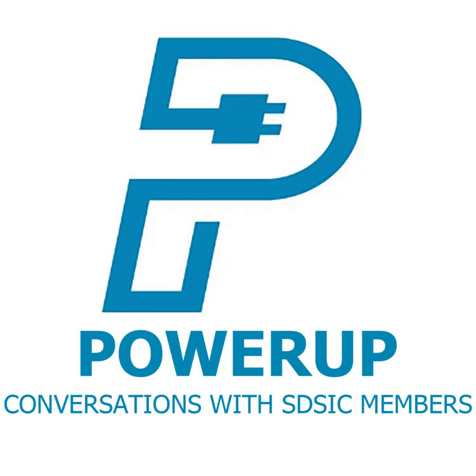The best thing you can do is scan a substation, because most substations are old. They have no drawings. They have probably been remodeled many, many times. You go to do something in a substation, it's energized. Usually the easiest thing to do is scan that station, and then you'll know where everything's at, where the conduit's coming out of the ground, all the things that are very important. What size bolts you have. I mean, the technology now is amazing.